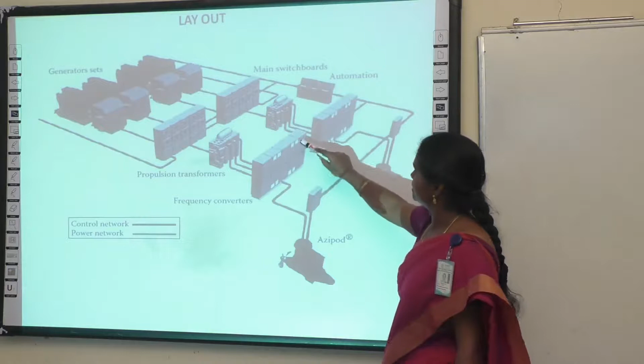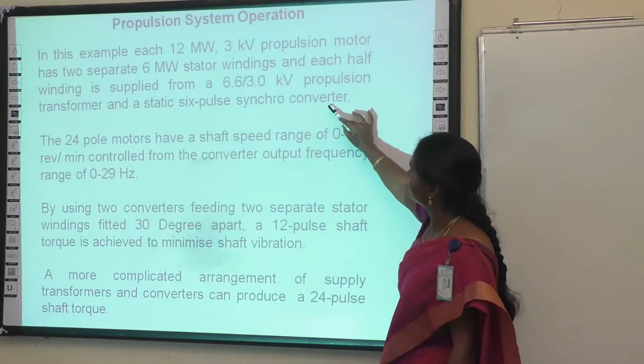Propulsion system operation. In this example, I'll show the diagram. Each 12 megawatt 3 kV propulsion motor has two separate 6 megawatt stator windings, and each half winding is supplied from a 6.6 kV 3 kV propulsion transformer and a static 6-pulse synchro converter. Again I am saying, this power electronic converter plays a major role here, which drives the motor. This propulsion motor is driven by this 6-pulse synchro converter.